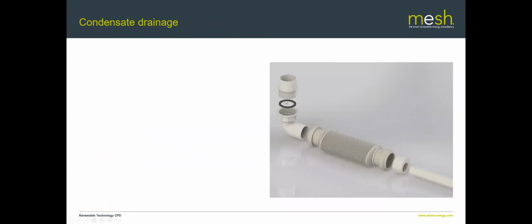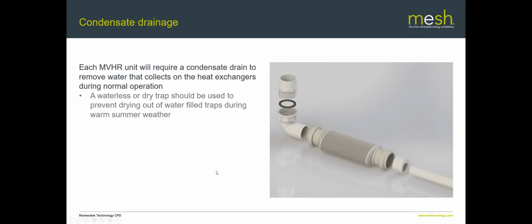And then finally, on this area, we talk about condensate drainage. Taking warm, damp, humid air out of a building and then cooling it down, you will then get condensate forming. That condensate needs to be drained away to somewhere, so it is worth considering where that condensate is going to go. There will be a little condensate drain connection on the bottom of each MVHR unit, and that typically just goes through a waterless trap and then to a drain.